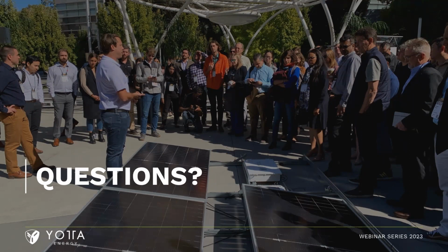All right. Got some questions about panels. Have you certified other solar panels to be used with the other Yotta components? Solar panels are agnostic. We really don't care. The SolarLEAF doesn't care. What I care about is the input voltage. The maximum input voltage is basically 50 to 60 volts. If it's below 60, we want it to be in that sweet spot, the MPPT range of anywhere between 22 and 48, which is the sweetest spot to make the maximum amount of power.